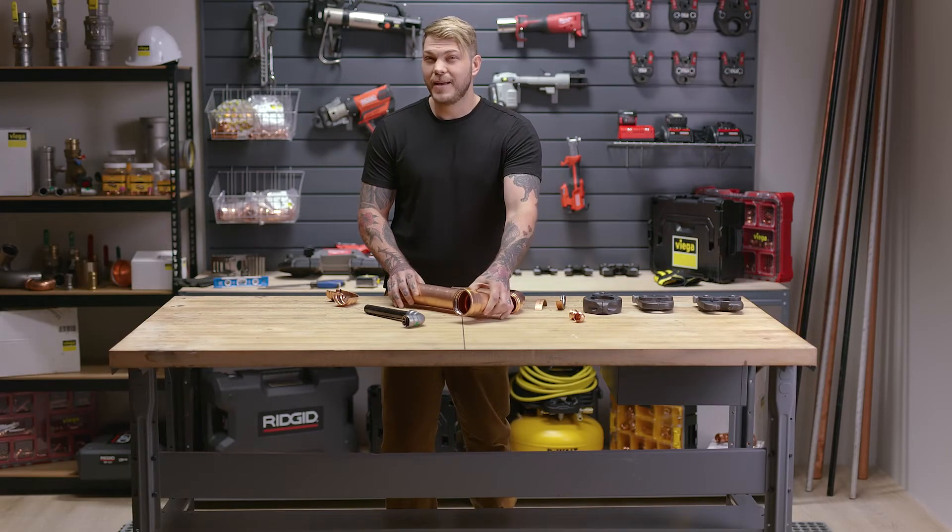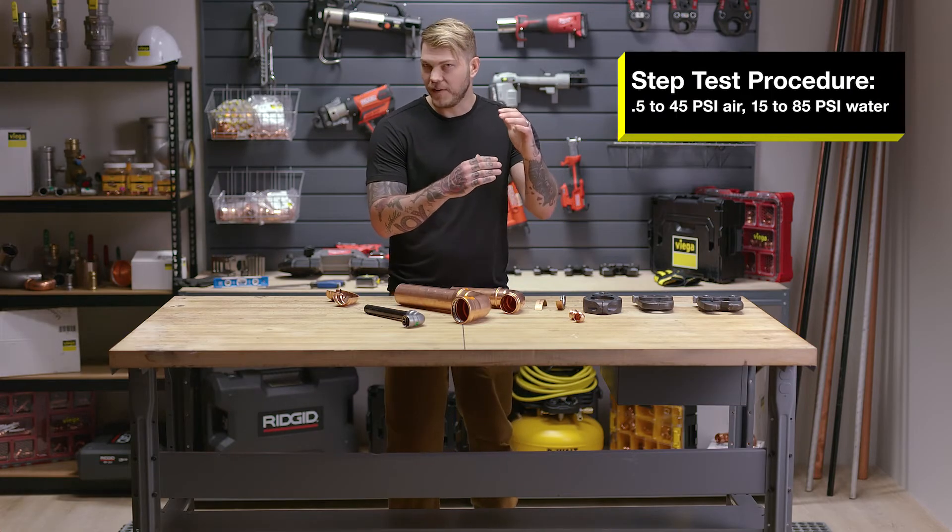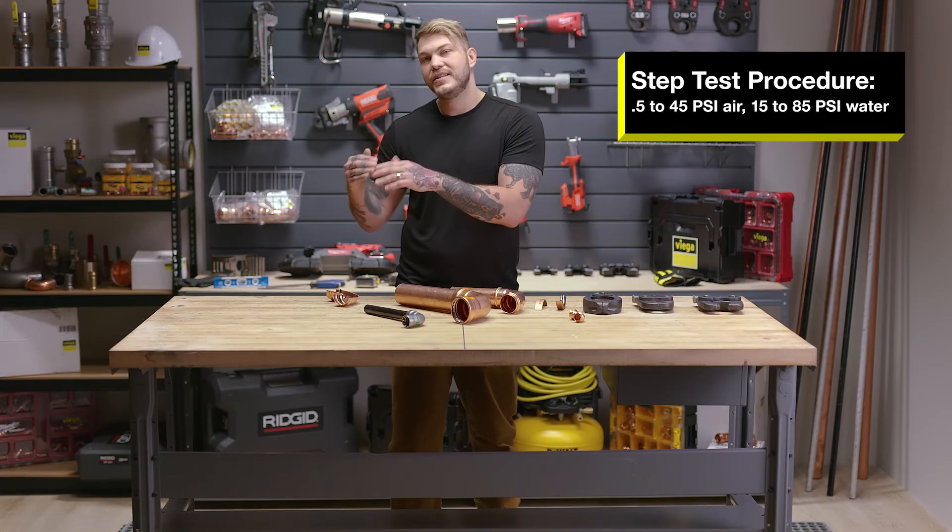What we're going to do is use a step test procedure. Your first test is going to be from half to 45 PSI air and 15 to 85 PSI water. Once you've identified that, you can take your test up to 200 with air or all the way up to 600 with water. And that's Viega's Smart Connect technology.